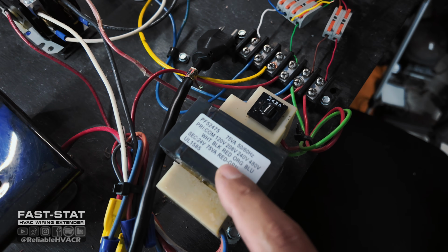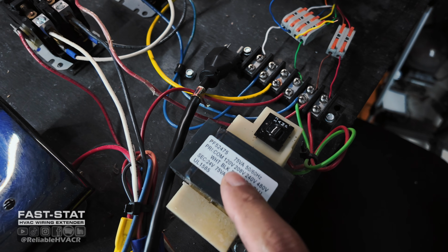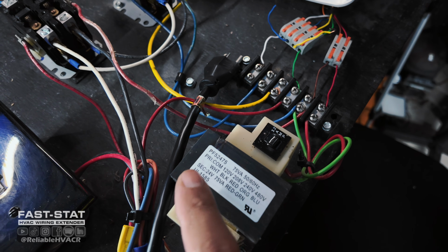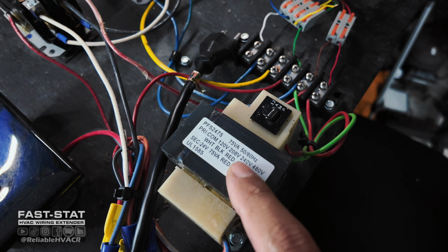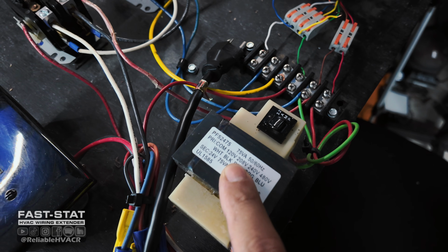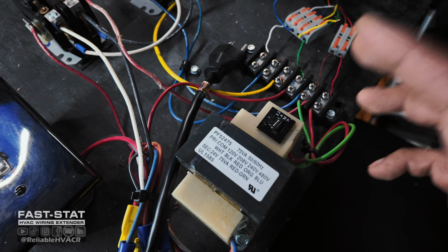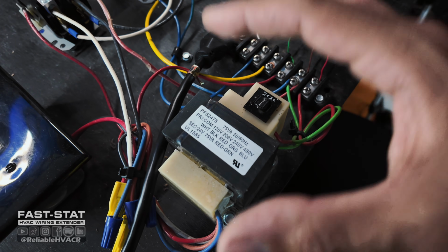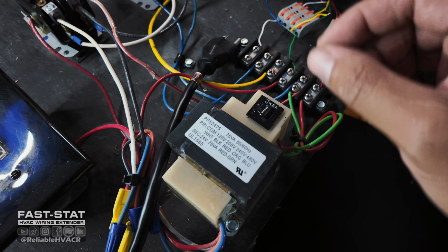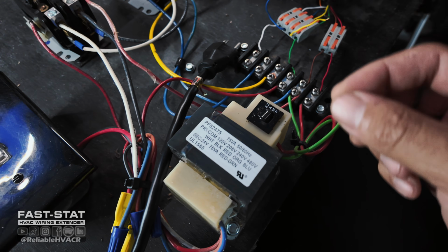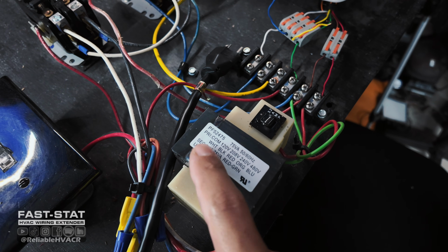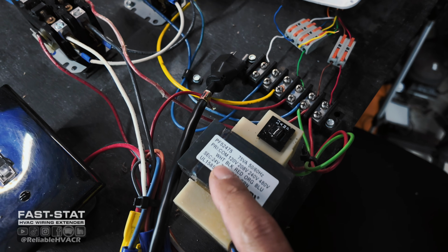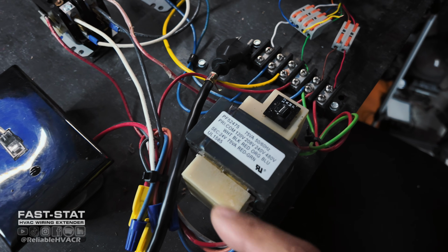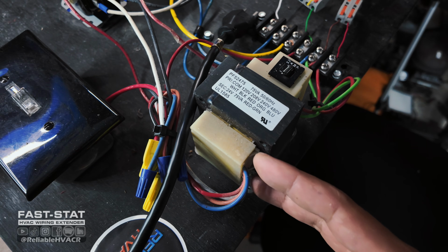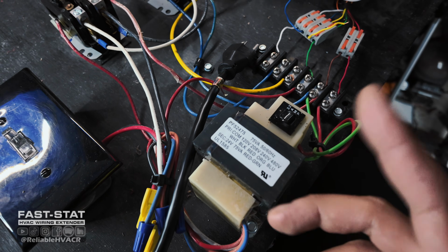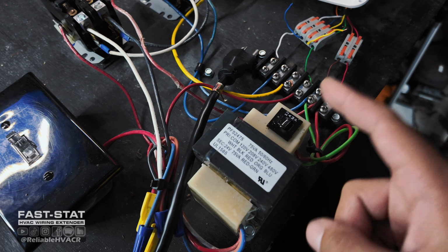It's basically an all-in-one. But if you have a transformer, especially on commercial, where it's 208, 240, and common, and it's installed and left on the 240 or 230, but you actually have a 208 system, you're going to get not the proper voltage on your 24. You might get like 18 volts, something off, where it's going to mess up down the line and you'll have intermittent issues. So always make sure if you're on commercial or you have any of these universal ones that you're tied into the voltage that is feeding it. That way you check, do I have 208, do I have 240, 120, whatever it is, and make sure that it's correct on both sides.